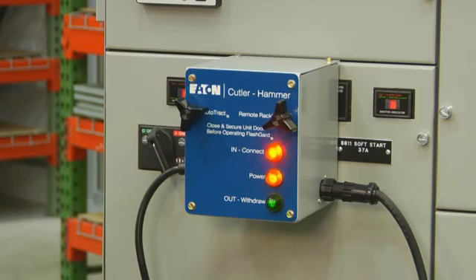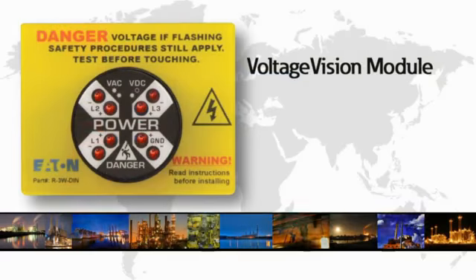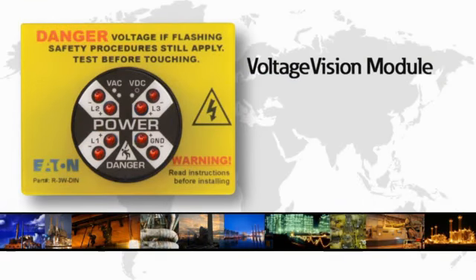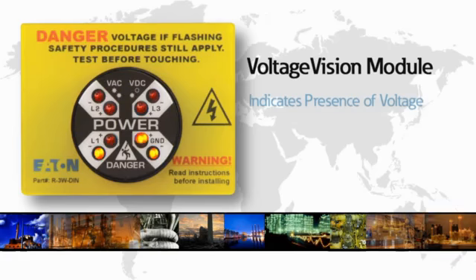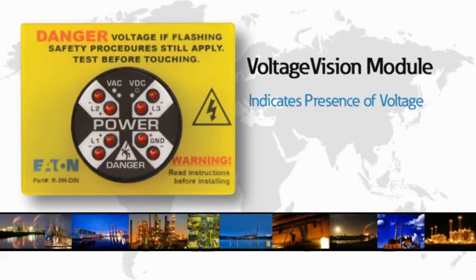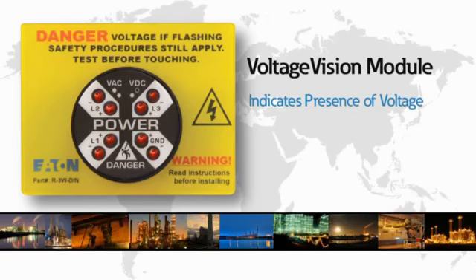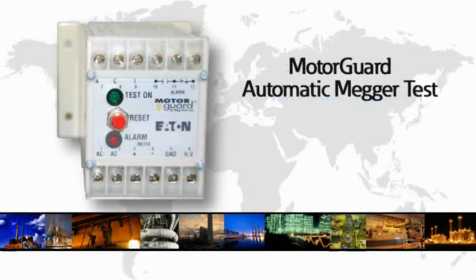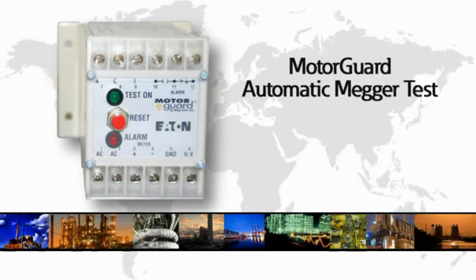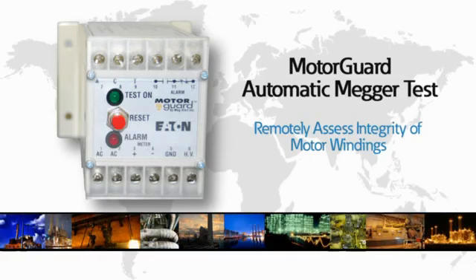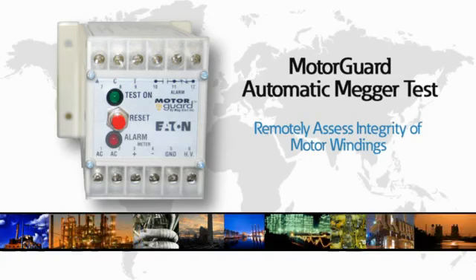An optional remote racking system extends the operator's safety zone to a maximum of 15 feet while disconnecting or reconnecting the unit power stabs to the vertical bus during bucket replacement. Available panel accessories also include the voltage vision module, which flashes to indicate the presence of dangerous voltages inside the unit, and the MotorGuard Automatic Megger Test unit that remotely assesses the integrity of the installation of motor windings while the motor is idle.